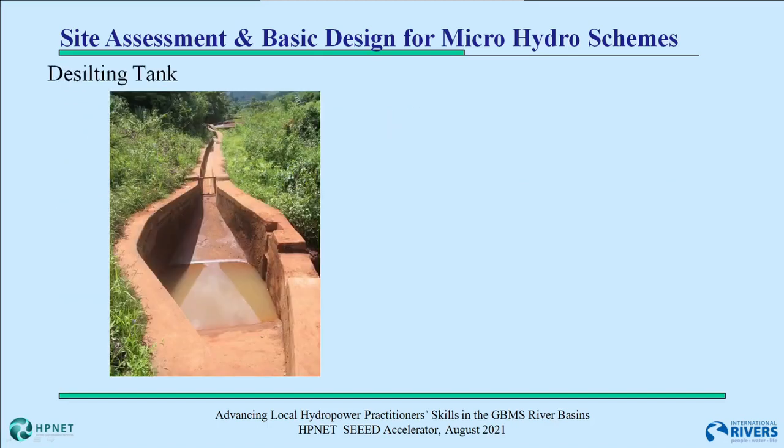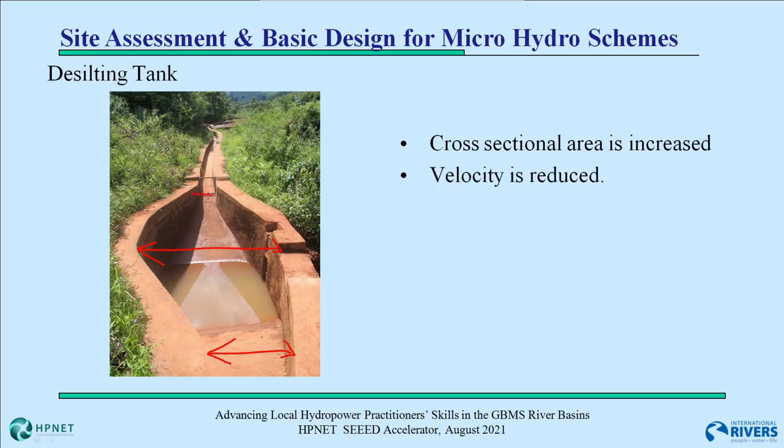The water from the stream carries small particles of solid matter. The silt load is composed of hard abrasive material such as sand and will cause extensive damage and rapid wear to the turbine runners. To remove this silt, the water flow must be slowed in the settling basin so that the particles settle on the tank's floor where the deposits can be periodically flushed out.